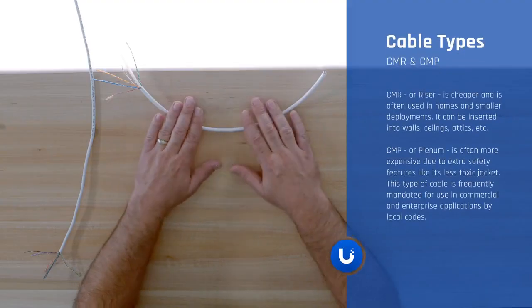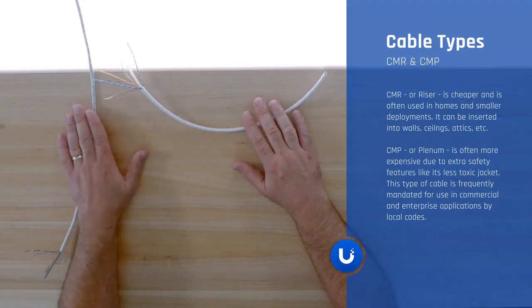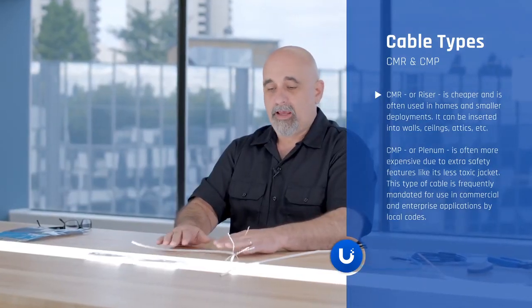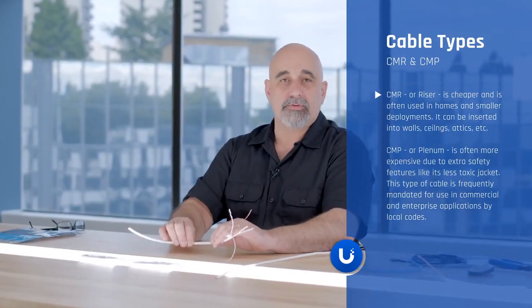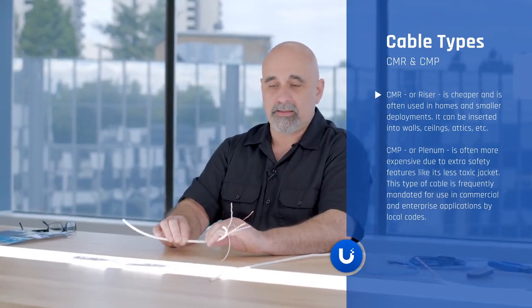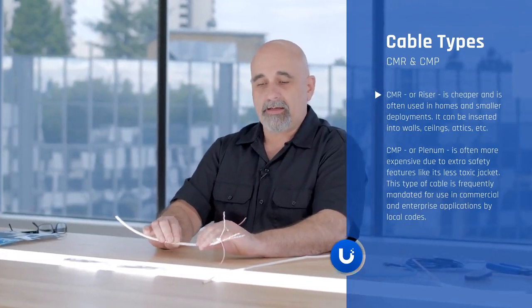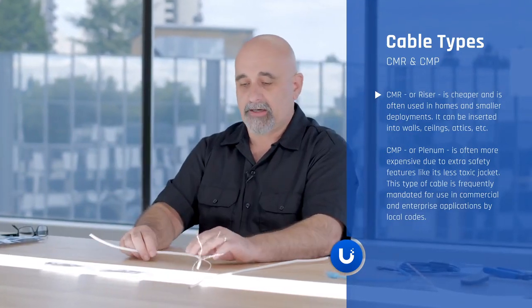There are also 2 different types of cable that you would use during your installations. There's CMR and CMP. R stands for riser, and that's going to be a cable that you're going to use in your house and in some buildings where it's allowed, and it's going to be able to go in your walls, through your ceiling, through your attic space.